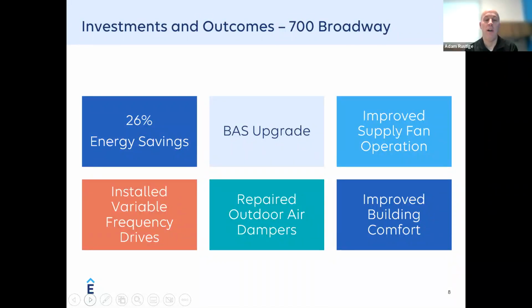Next, we installed a total of 12 variable frequency drives, controlling 270 horsepower of pumps. VFDs are a wonderful way to save energy. Also, the outdoor air dampers were in need of repair. This building was a combination of DDC and some pneumatic. These outside air dampers were pneumatic, and some of the actuators were no longer working. So we were able to convert those with new actuators and pull them into the current building automation system. That allows you to take advantage of outside air for free cooling and gets the outdoor air dampers to work as intended.